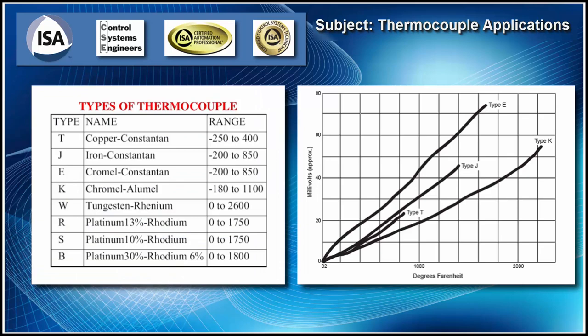Looking at the chart on the right, we can see what the millivolts are on the Y approximately compared to the degrees in Fahrenheit on the X-axis. And we can see that these thermocouples are not very linear. They're kind of non-linear all over the scale. And they take care of this linearity pretty much with software and lookup tables. But an RTD in itself is very linear. So the next thing we'll look at is an RTD, and it's more of a precise temperature measurement.